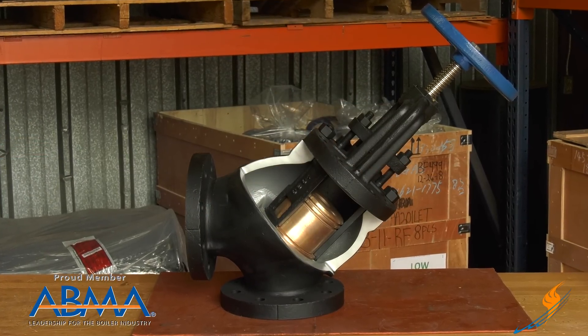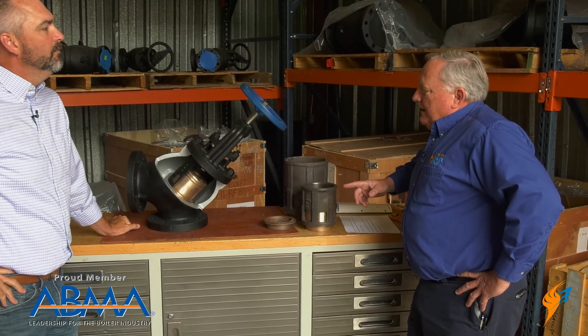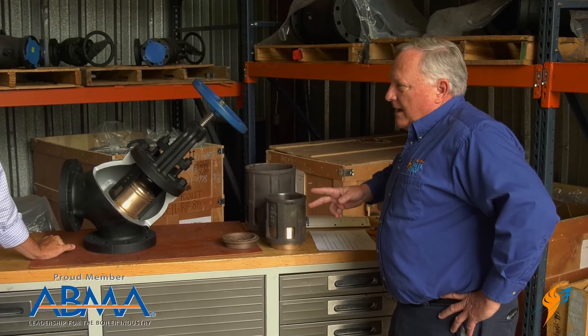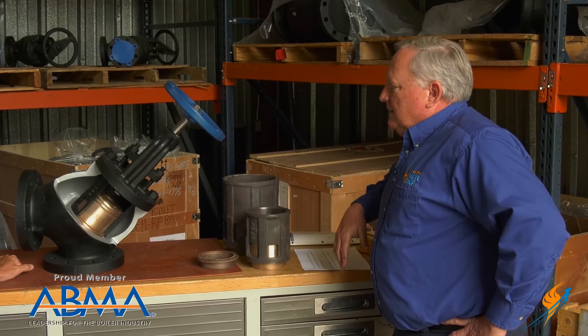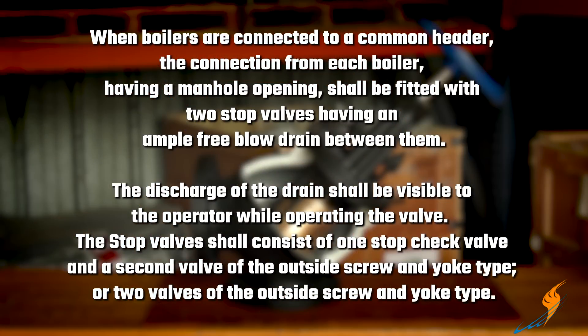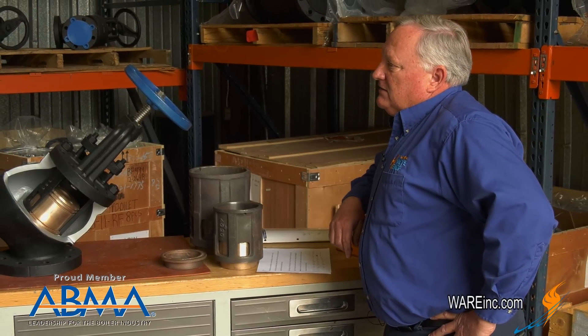They can be required by the ASME Section 1 code, and they're commonly called by two different names: one is a non-return valve, the other is referred to as a stop check valve. The boiler folks tend to call them non-return valves. The ASME code states that when boilers are connected to a common header, the connection from each boiler having a manhole opening shall be fitted with two stop valves having an ample free-blow drain between them. The discharge of the drain shall be visible to the operator while operating the valve. The stop valve shall consist of one stop check valve and a second valve of an outside screw and yoke type, or two valves of the outside screw and yoke type.